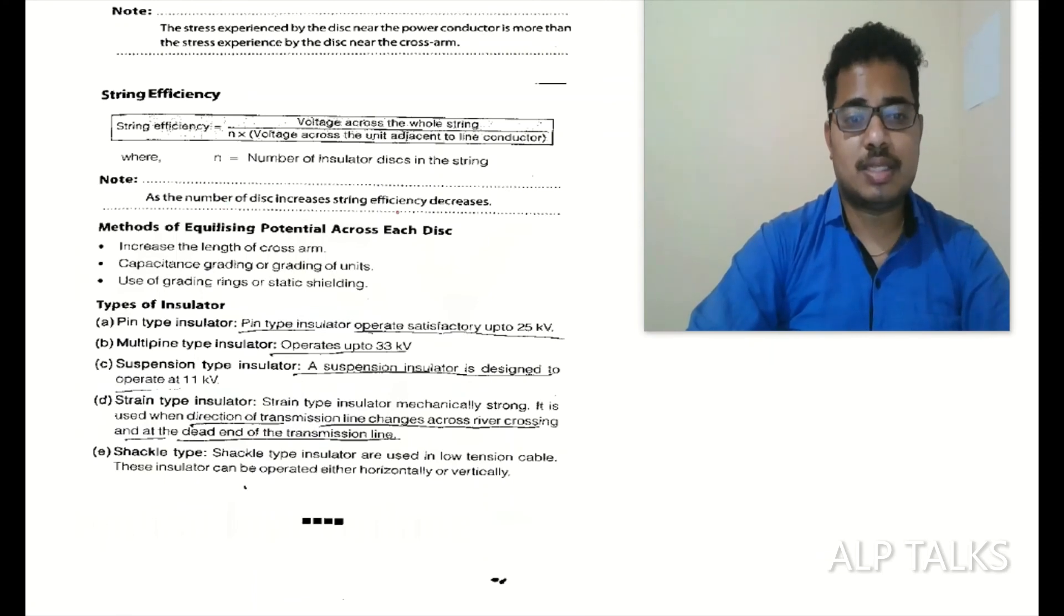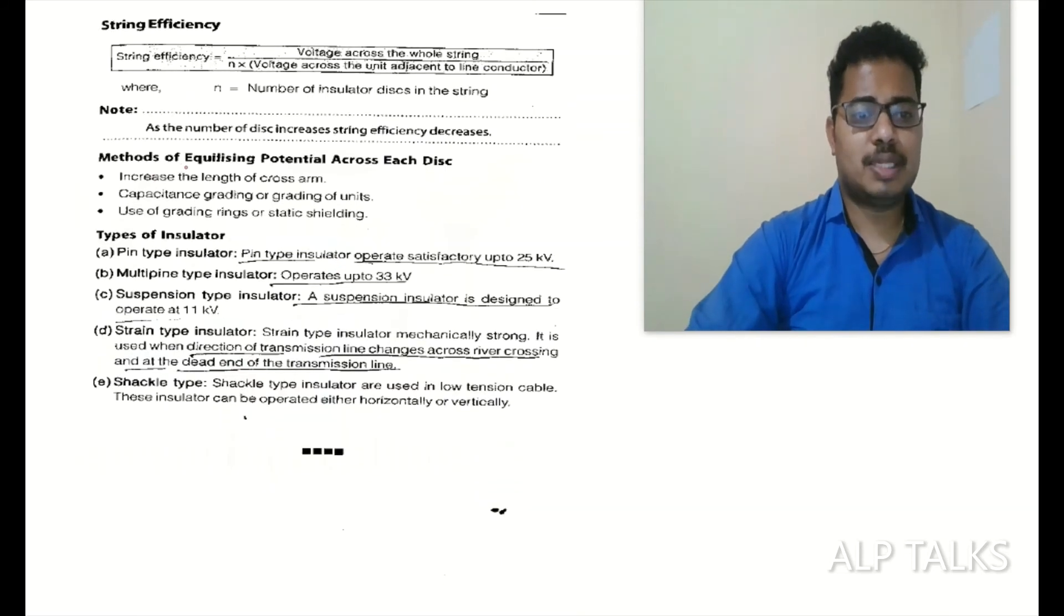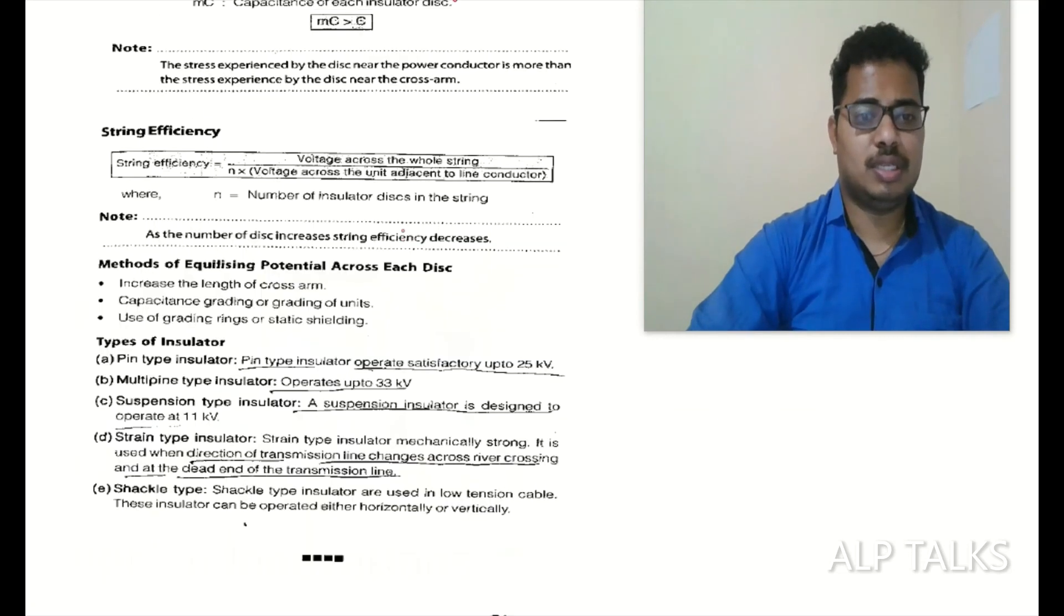As number of discs increases, string efficiency decreases. Methods of equalizing potential: increase the length of cross arm, capacitance grading or grading of units, use grading rings or static shielding.